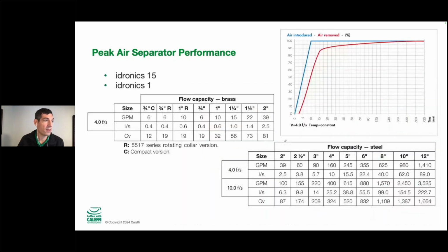Here is the performance of these separators. One of the things that we talked about before the webinar started is that one of the reasons we don't have a potable water air separator is because they're multi-pass devices. So if we had a low lead 1-inch air separator that you put on the inlet of the water coming into your building, we don't have multiple passes there. We have a single pass. So we're going to get some of the air out, but at a single pass, we haven't removed a high percentage of air. It's going to take a few seconds in this graph, or a few minutes depending on the system size and volume, to get all that air out.